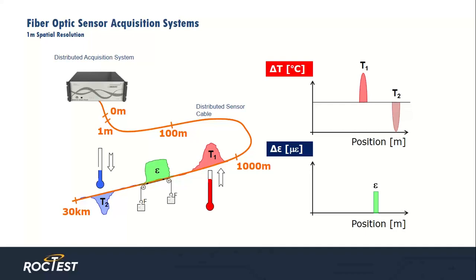Backscatter light provides a measurement point every meter along the cable. Therefore, we can sense everywhere along the sensing cable and localize defects. The Dynetis interrogator has a measurement range up to 30 kilometers and more, and can detect and localize changes in strain and temperature. The advantages of the distributed technique include a large number of monitoring points over a single optical fiber sensor, along with high resolution and accuracy.